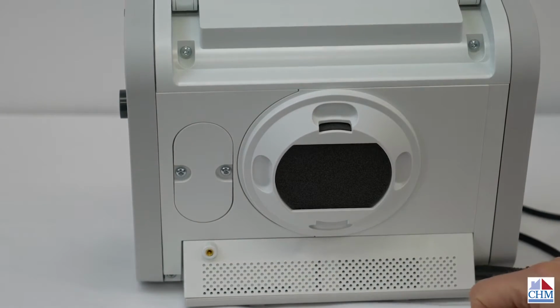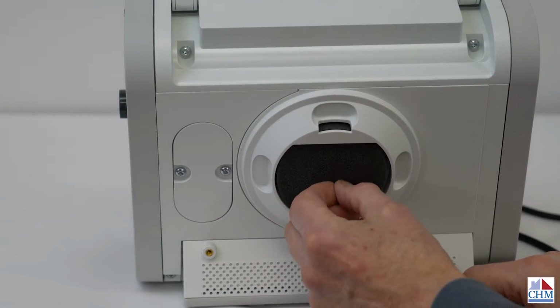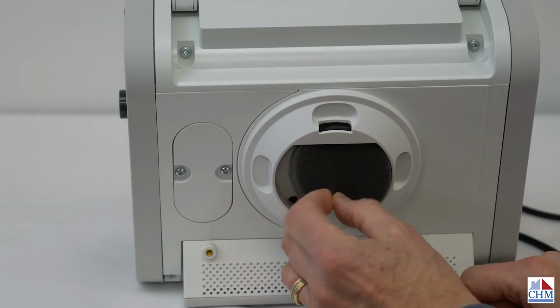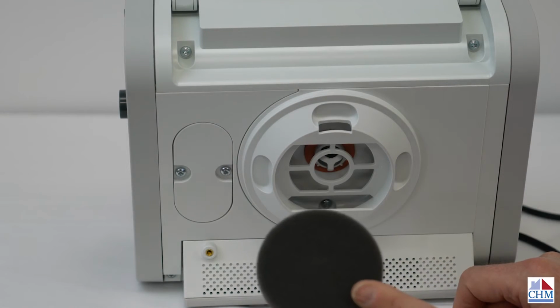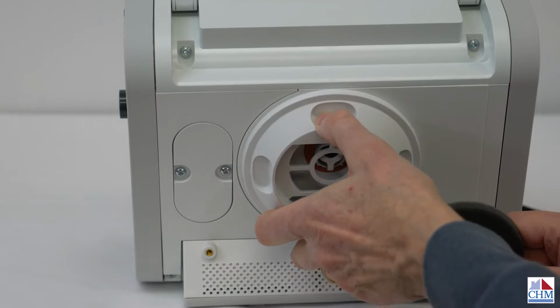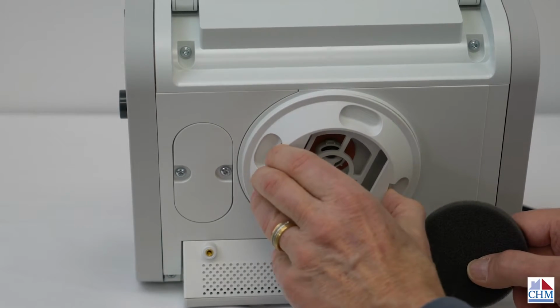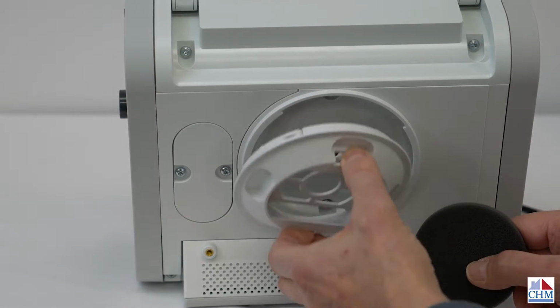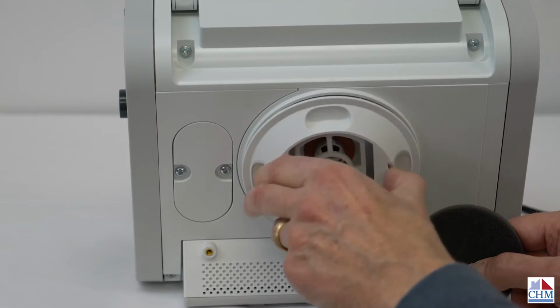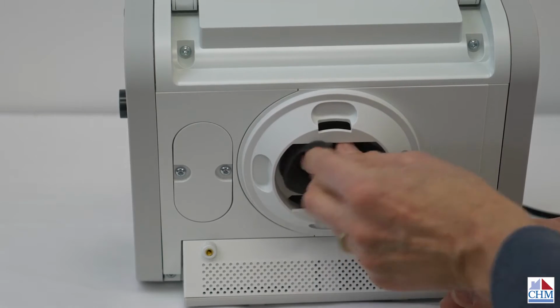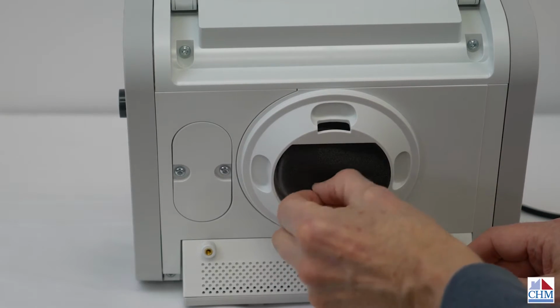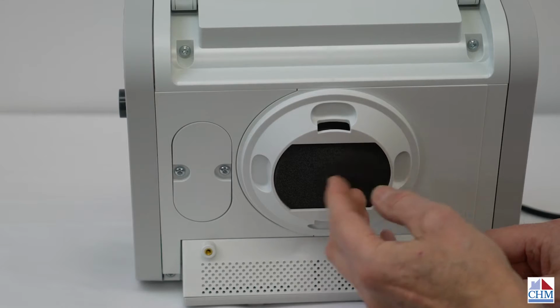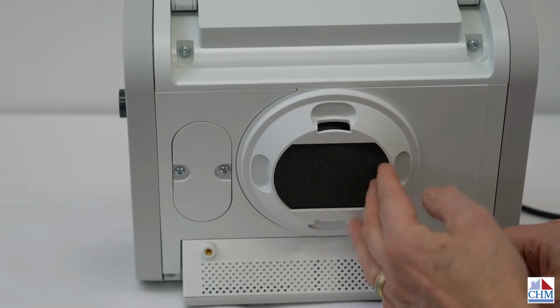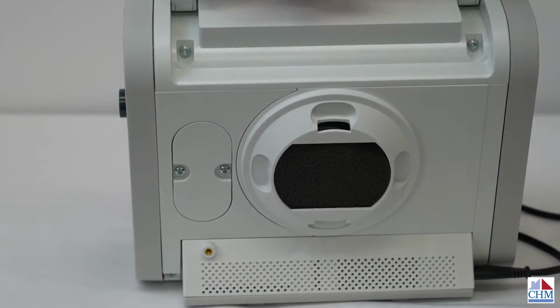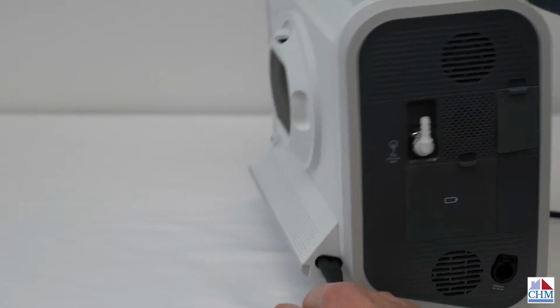And we've got a washable filter, notably larger than the Trilogy. A large filter here can also be taken off, and there's a cap that goes on also. That can be screwed back into place, so you can do that either way. Take that out and clean it. Of course, with all filters, make sure that they're very dry before they go back in. It just attaches here.